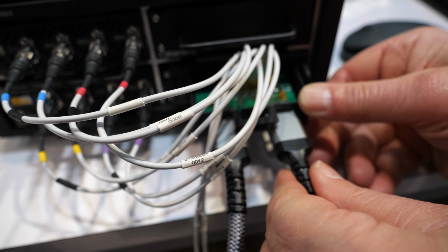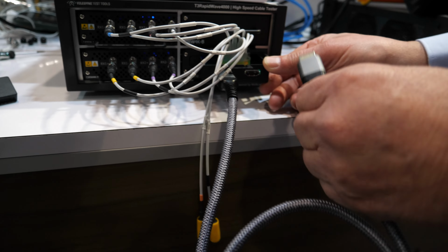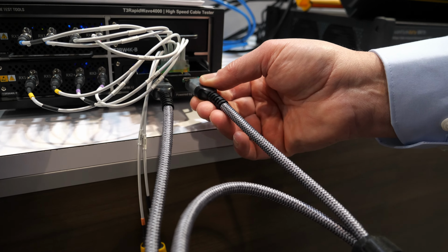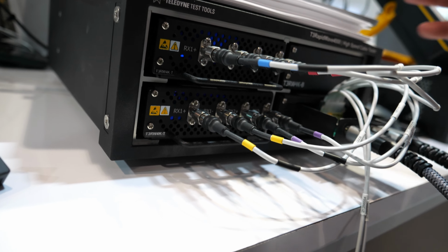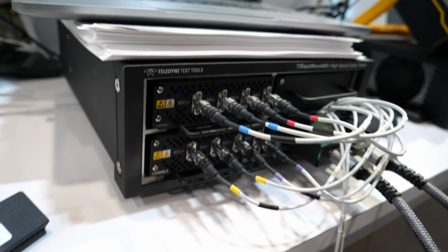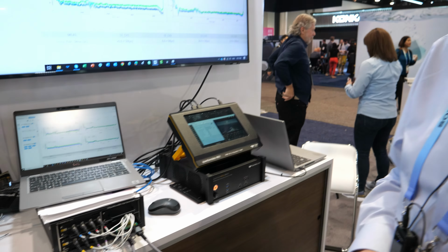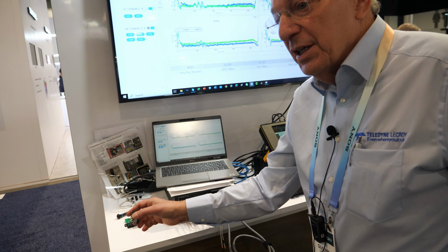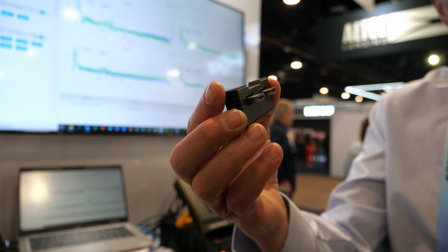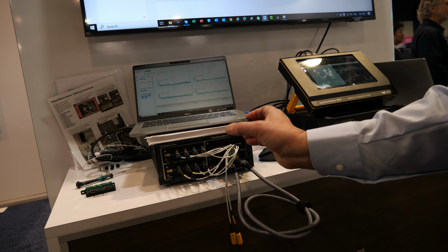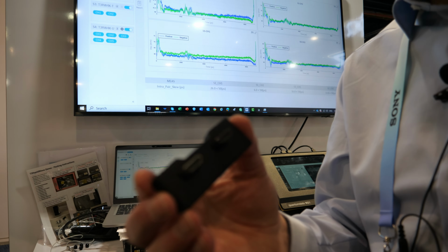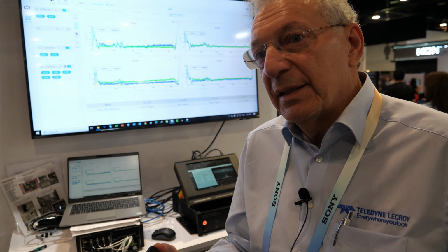So it's connected to the board that you have there, and all the cables go out and back in? Yeah, basically the only thing is just to plug the cable into the system, and that's it. What you see here is just the setup that has to be built from the beginning. Then you don't have to take care of anything else. To do the calibration is very easy. This is the calibration kit that you plug in instead of the cable, and the calibration is done. So what I'm saying is that we are also making it easier to get a completely calibrated system.